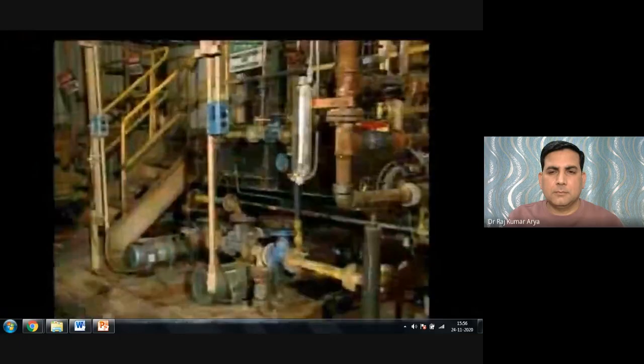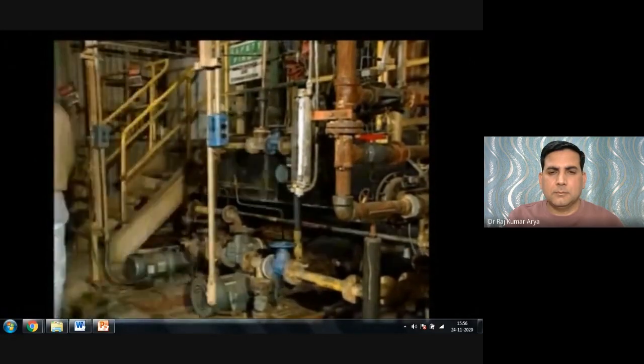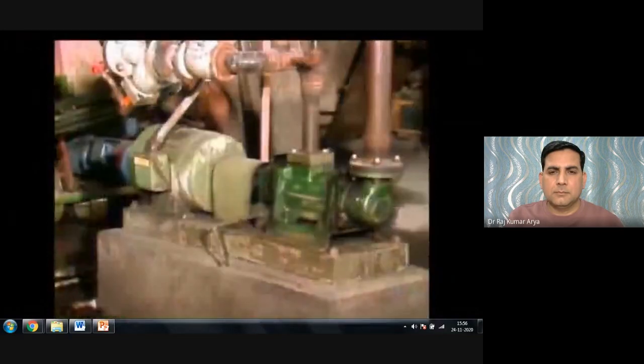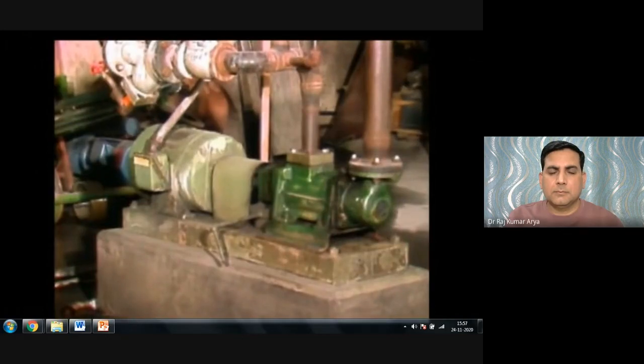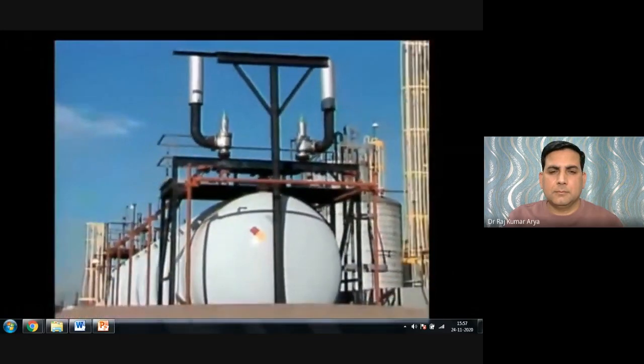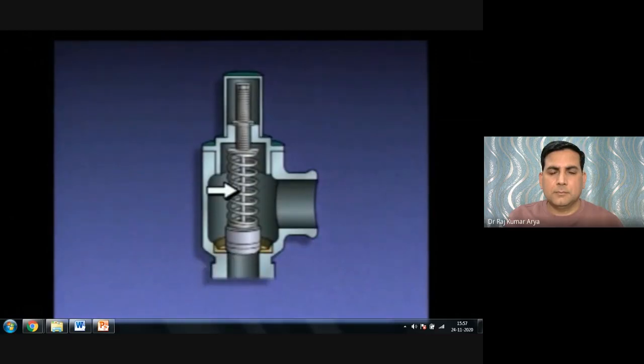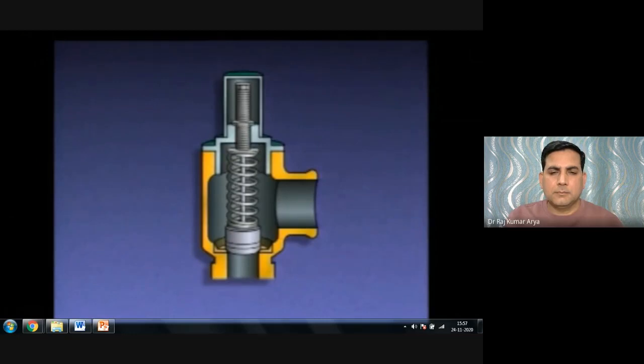Excessive pressure can occur for various reasons, such as starting or stopping equipment without proper valve positioning, or equipment malfunctions. For example, if a line from a pump is blocked when it should be open, pressure can build up. Excessive pressure can be relieved by relief valves. A relief valve consists of a valve body, a disc, a seat, a spring, a valve stem, an adjusting screw, and a lock nut.